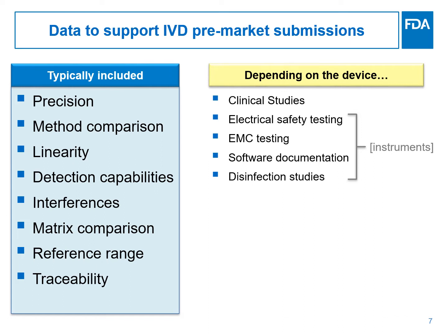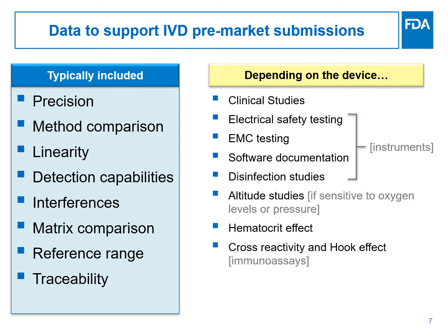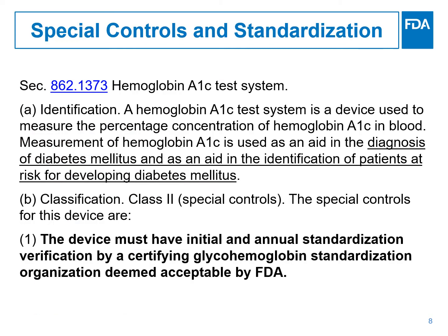And again, depending on the device, it may require other studies, like altitude studies, assessment of hematocrit effect, cross-reactivity and hook effect, biocompatibility, sterilization, and the list can keep going on and on. Please note that although this list seems very long, it is not all-inclusive. FDA acknowledges and agrees that standardization or harmonization processes where the accuracy, precision, and other analytical performance parameters are improved, maintained, and independently verified will in general be beneficial to patients. And I will share two examples with you.